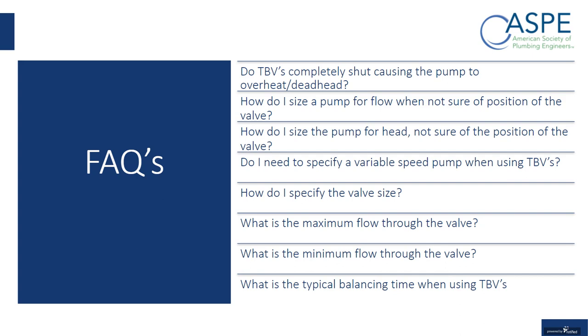How do I specify the valve size? You match the line size. What is the maximum flow through the valve? You look at the maximum CV of the valve, you assume a pressure drop, and then basically you determine what the maximum flow is. What is the minimum flow?